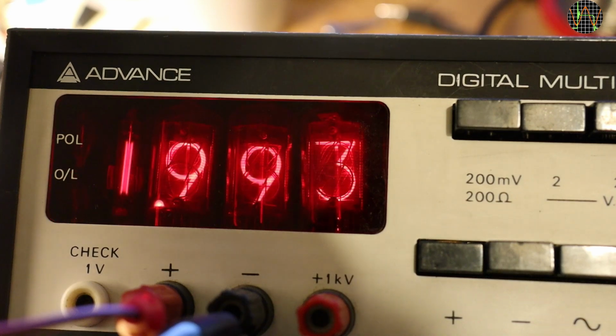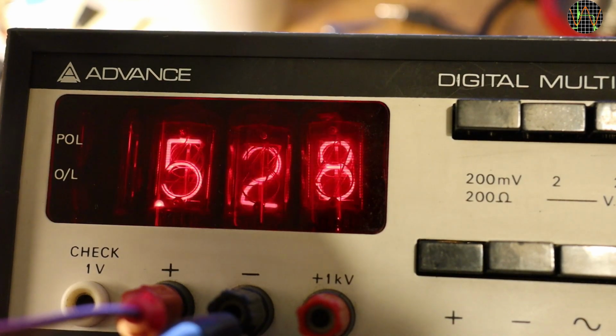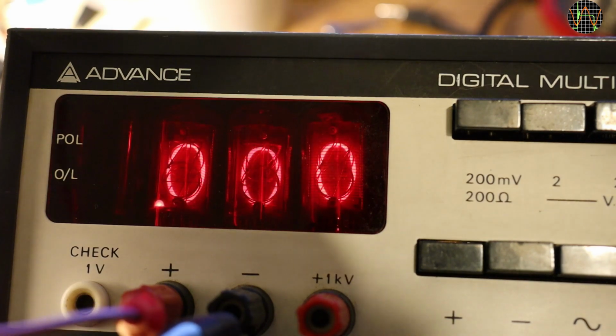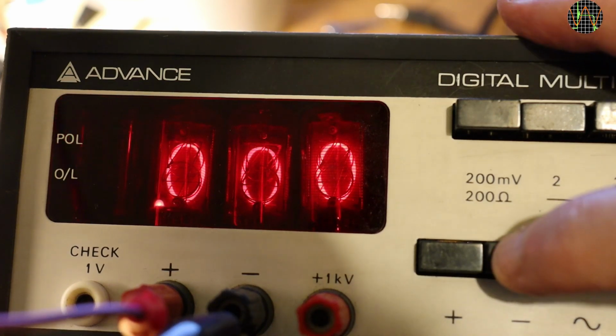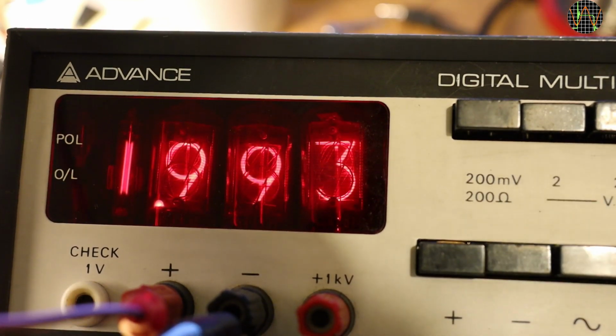If I now reverse the polarity at the input, the displayed voltage kind of drains away, but only on the display. I have not reduced the voltage, it's still 1.993, I simply swapped the polarity. I can now either swap the leads or press the minus button, which swaps them internally, and the display is back. Notice that the only indication that you are now seeing a negative voltage is that the minus button instead of the plus button is pressed. This is easily overlooked. Coming from modern digital meters that simply show a minus sign automatically, this behavior of the DMM2 is definitely another thing you have to get used to.